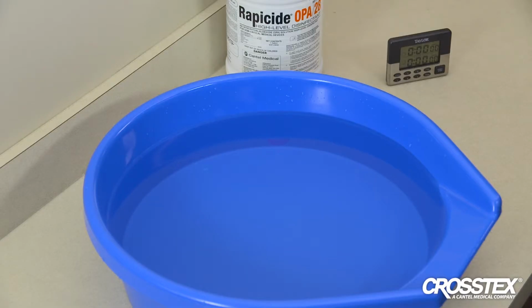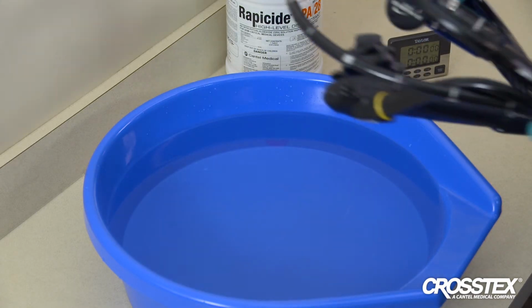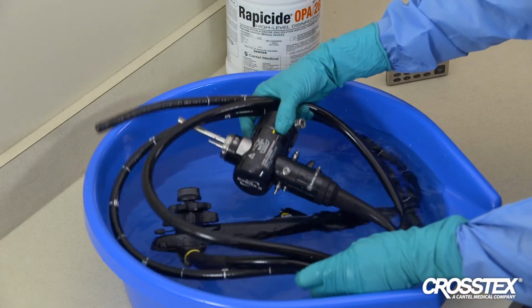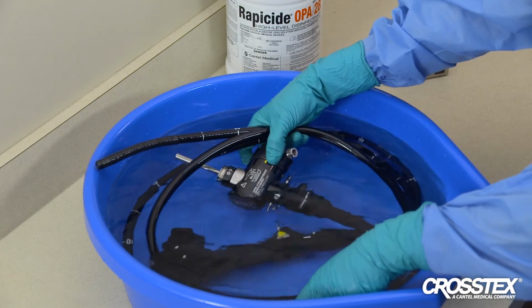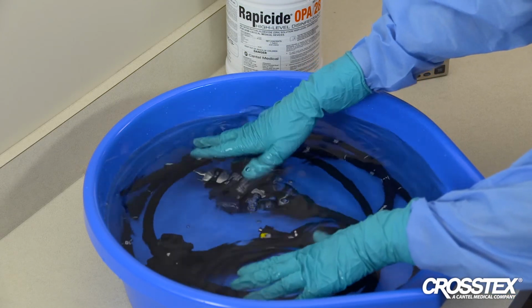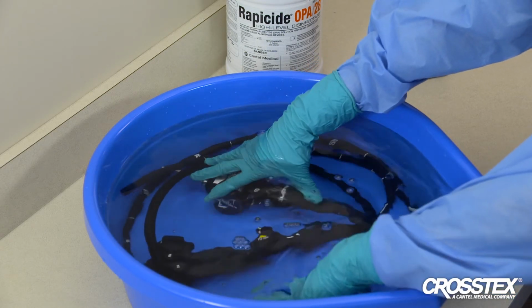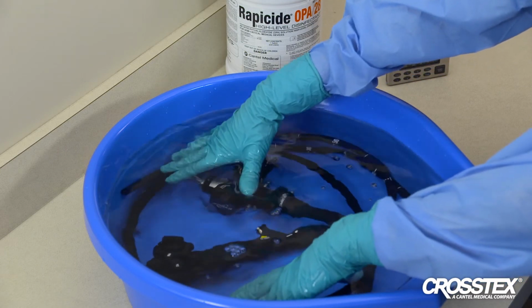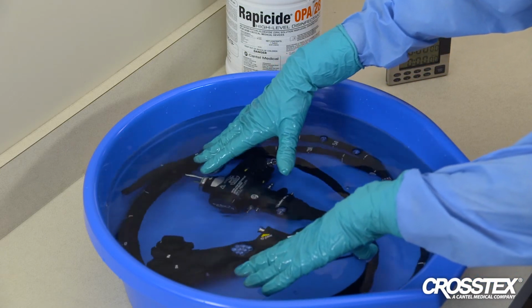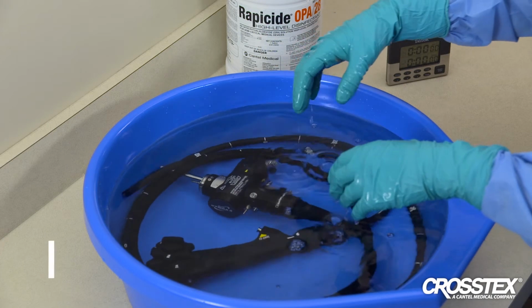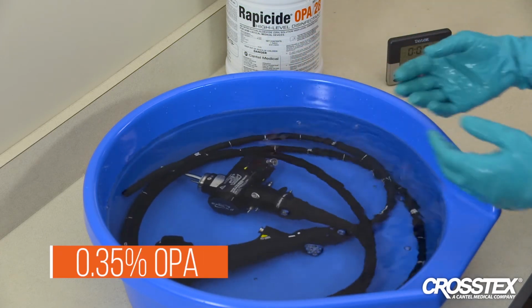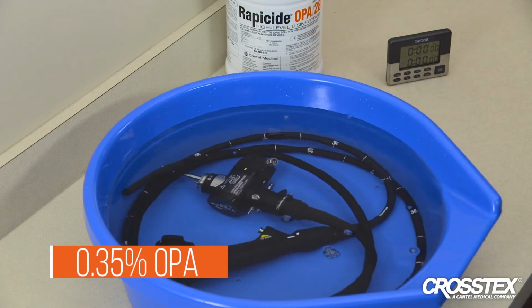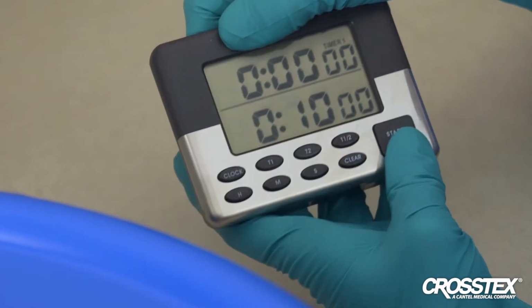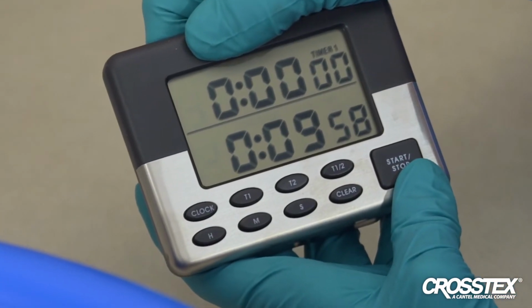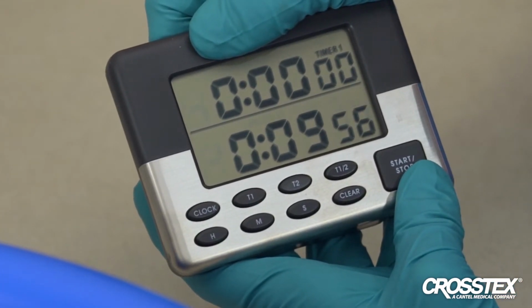Follow the same steps as before for testing the MRC of the Rapicide OPA 28 HLD solution. Place the pre-clean scope into the manual holding tank that contains the Rapicide OPA 28 HLD solution. Immerse the device completely in the Rapicide OPA 28 HLD solution at or above 0.35% OPA for a minimum of 10 minutes at room temperature, which should be a minimum of 20 degrees Celsius. Make sure all lumens are filled.